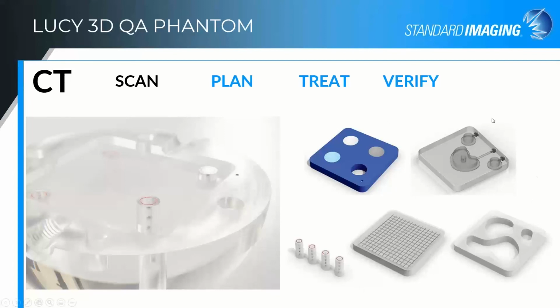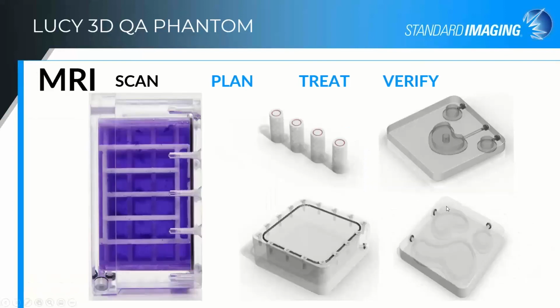These are some of the CT scanning inserts. We have fiducial markers, image distortion grid, different densities, and then targets, and there's a BB in this one, irregular shaped and regular shaped targets. Same thing for MRI. We have a larger distortion grid, as well as localization markers that align perfectly well.